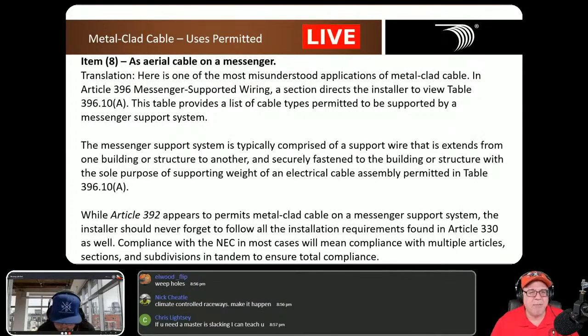Number 8, aerial cable on a messenger. Translation: here is one of the most misunderstood applications of Metal-Clad Cable. Article 396, which is messenger supported wiring. It directly states in 396.10(A) all the different types of cable methods that can be supported from an aerial messenger system. And of course, in that list in 396.10(A), go check it out, you'll see that MC cable is listed there. So again, if it's outdoors, it's PVC jacketed MC, it's being supported independently from a messenger support system, then you're okay to run MC cable for that application. Again, wet location, PVC jacketed, got to meet all those rules, but yes, okay to do that.